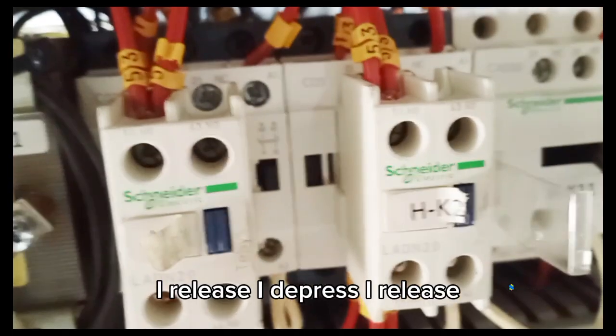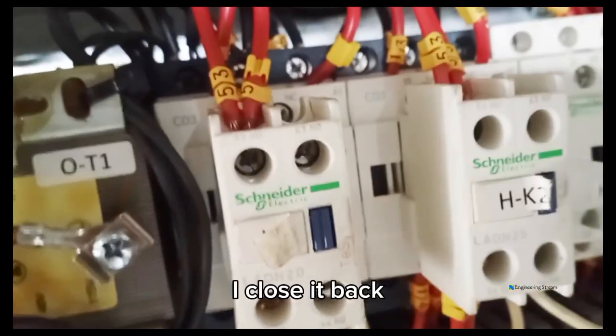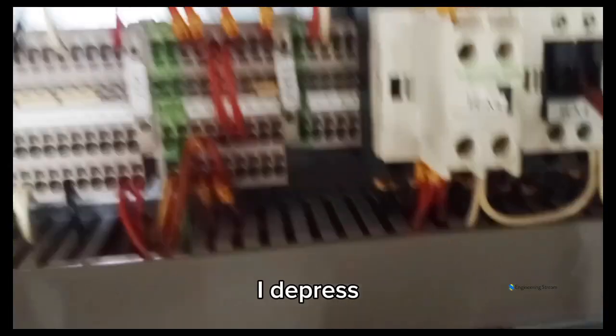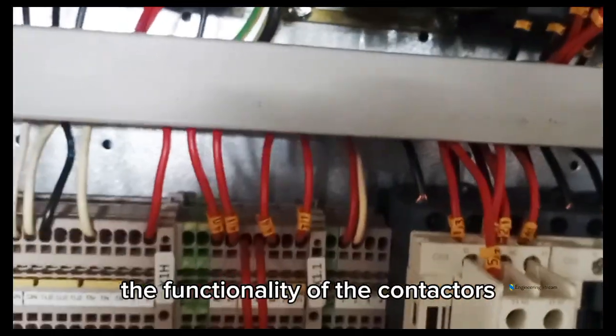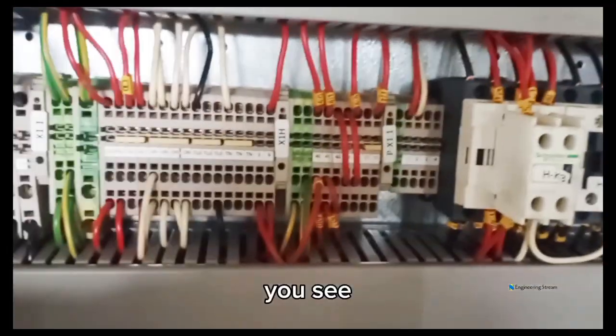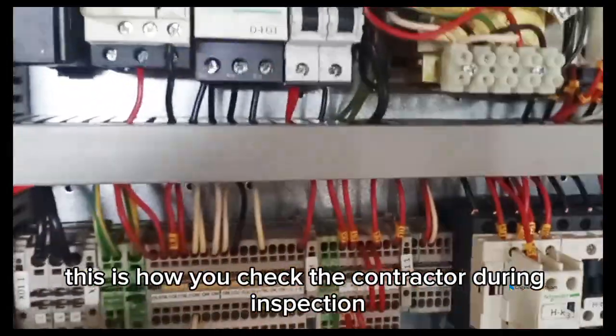I come to another contactor. This one here, I depress, I release, I depress, I release. I close it back. I come here, you see, I depress, I release. Hear that noise? I release. I depress, I release. I come back to this one here, I depress, you see, it's making and coming out. You see, what I'm doing, I'm checking for make and break, the functionality of the contactors, if any is due for replacement. This is how you check the contactor during inspection.